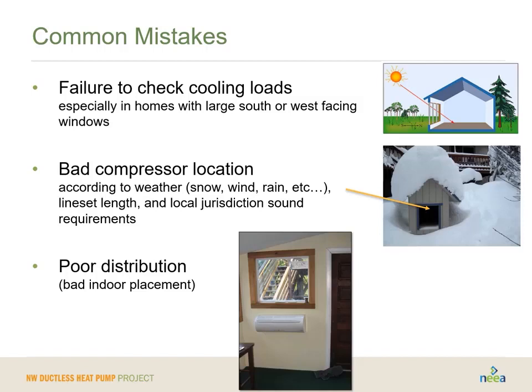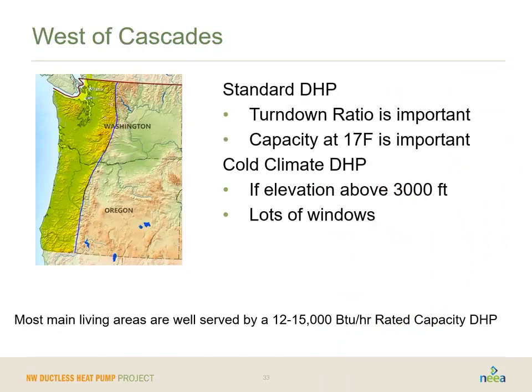And this means potentially using the right piece of equipment for the right location. In this scenario, if the only place to put the indoor head in this main body was somewhere low on the wall, then don't put in a head that's designed for high on the wall. They actually sell floor-mounted units that could be installed right down at the bottom. So picking the right piece of equipment is a critical piece to not having one of these common mistakes.